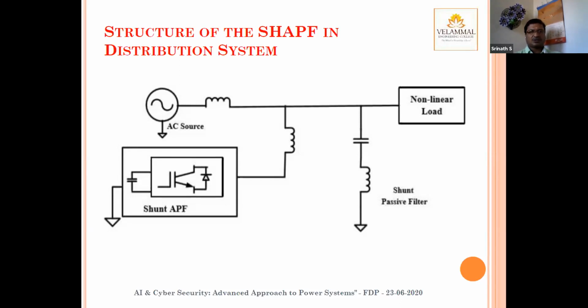So in order to improve the power quality, we can connect an active power filter. Mostly the current quality problems are taken care of by the shunt active filter. Here, in addition, we have connected a passive filter also for selective harmonic elimination, specifically for 5th and 7th harmonic elimination. I think you know the advantages.